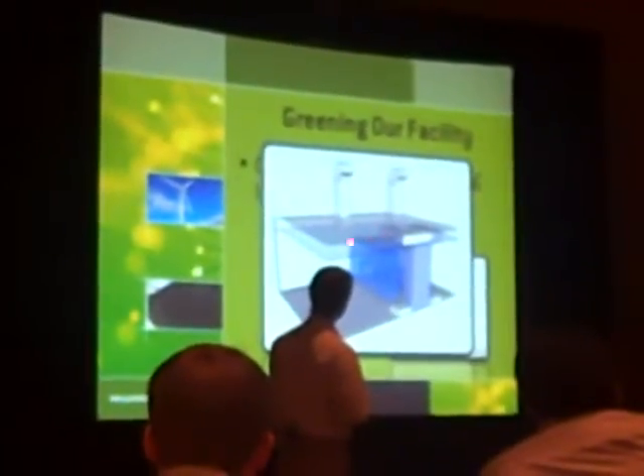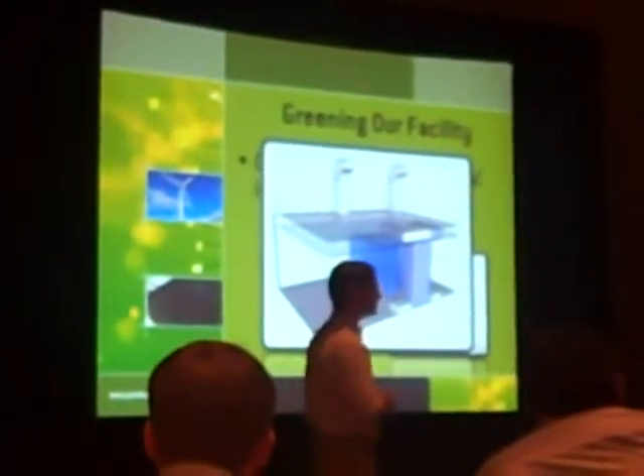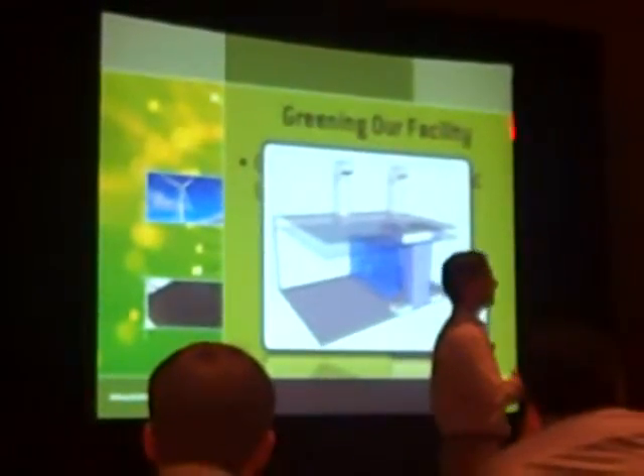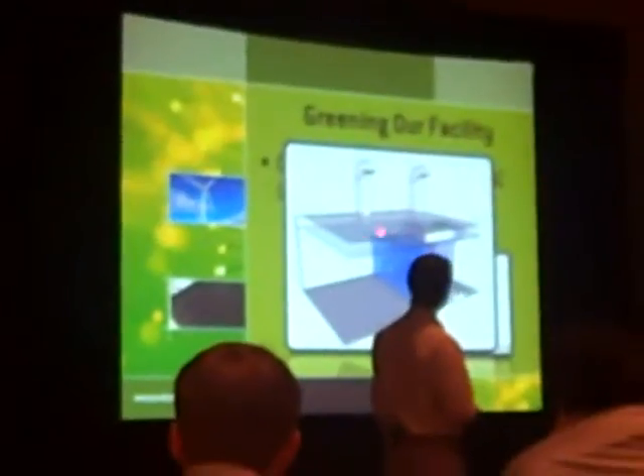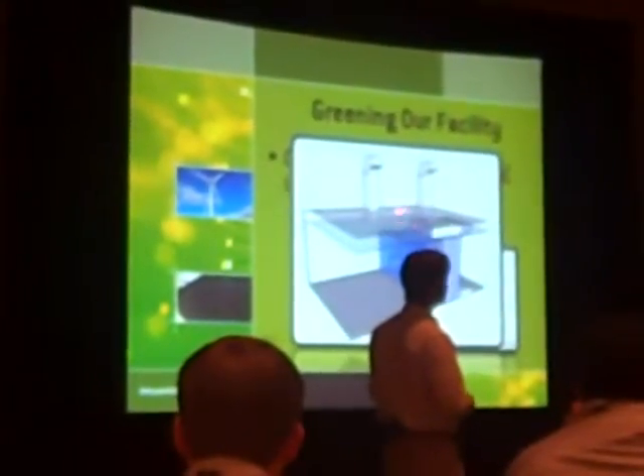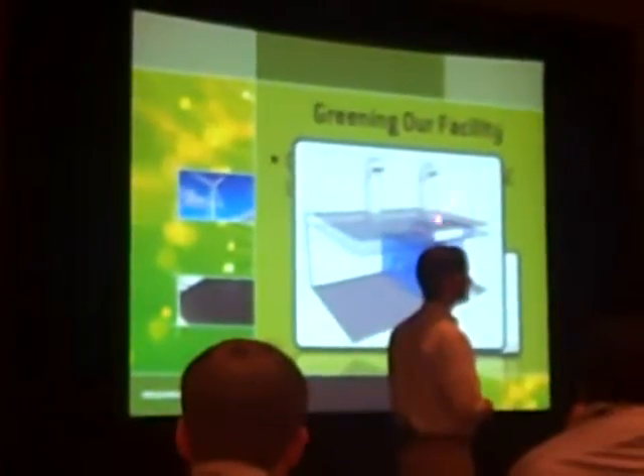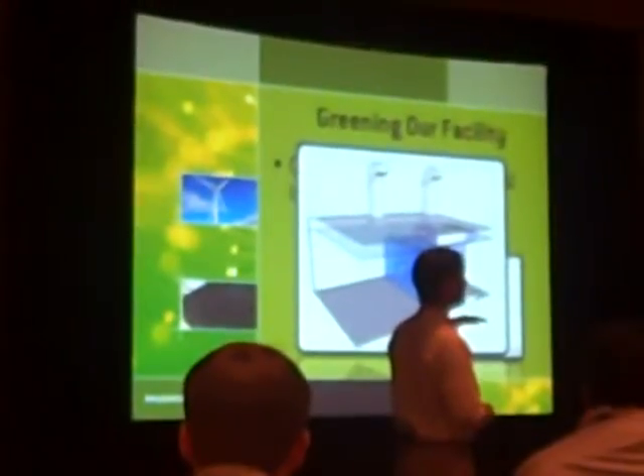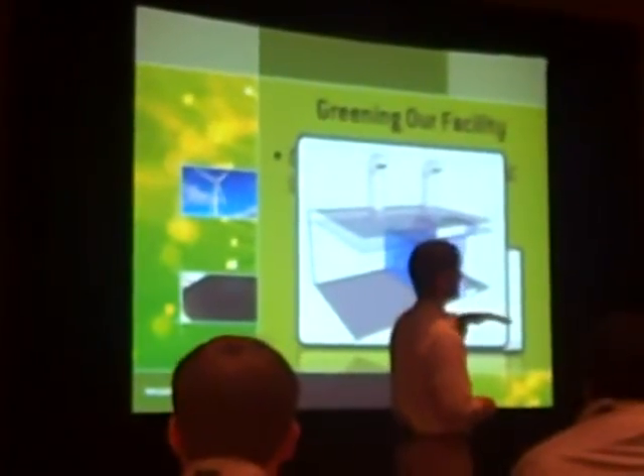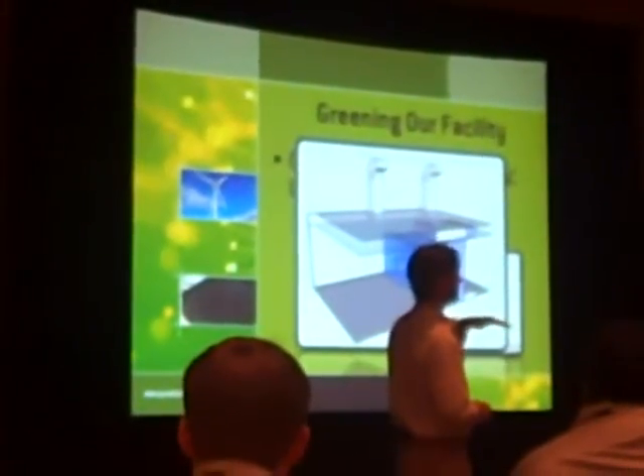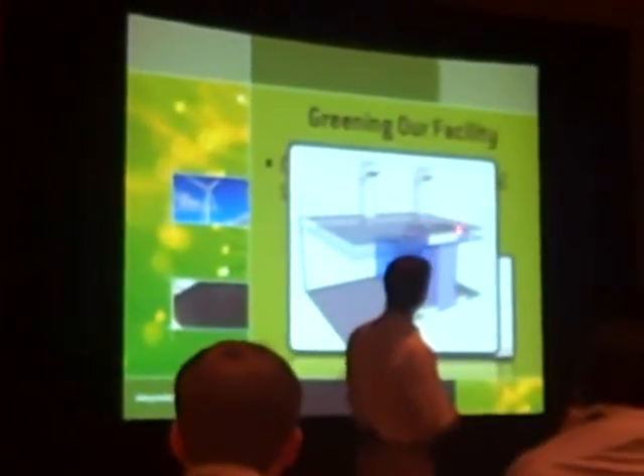So what we then do is pull in the air when it is minus 10 or 0 or 30 or 40 for that matter. We then allow the appropriate amount of air to come into our hot plenum in the ceiling, mix in the ceiling to bring that temperature back into the 65 to 68 degree air temperature.